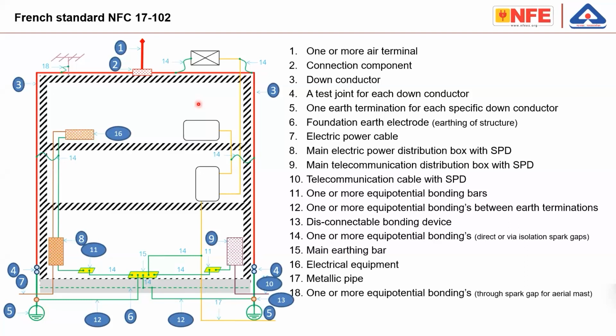17102, the lightning protection consists of serial numbers 1 to 18. It consists of one air terminal, which is nothing but the serial number 1, an ESE rod, then connection components, outdoor down conductors, several down conductors, and you see a lot of equipotential bonding and so on. So the French standard says this is how you should make a lightning protection system, and the Indian standard says this is how you should make a lightning protection system, but the serial number 1 is not required. The serial number 1 is about early streamer emission, whereas serial number 2 to 18 is the actual safety measures. The Indian standard says you don't need serial number 1, whereas the French standard says you need 1 to 18.